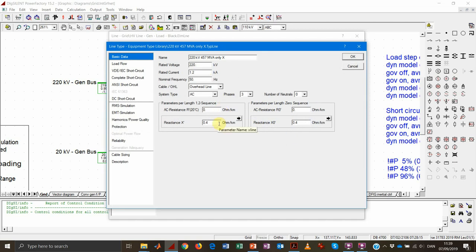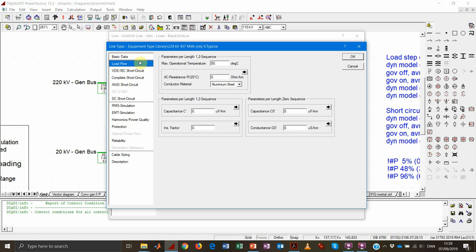The reactance — the inductive part — is 0.4 ohm per kilometer. The values are split according to positive, negative (sequence 1 and 2), and zero sequence. Since we are analyzing only balanced systems, we don't need to worry about the zero sequence values. The capacitive aspect of the line can be set under the load flow section, and right now the line has no capacitance at all.